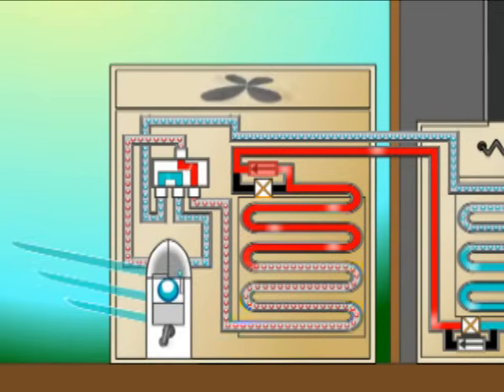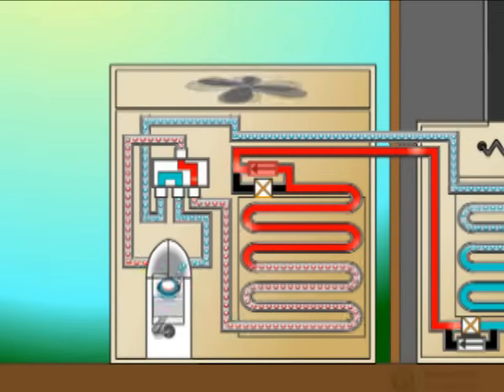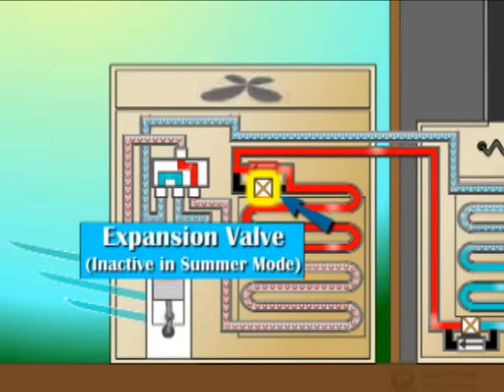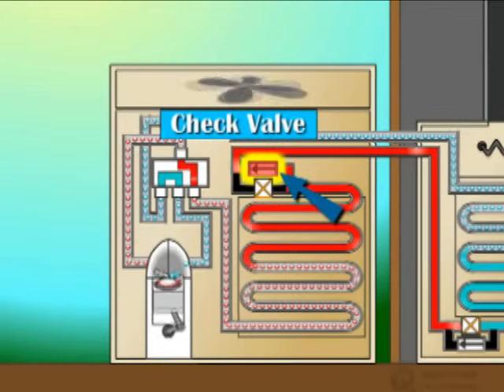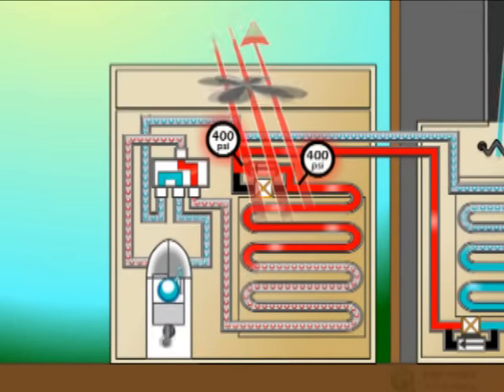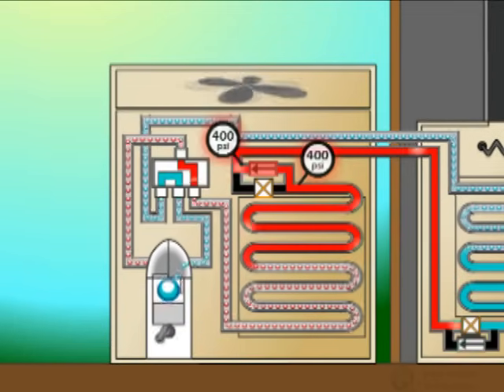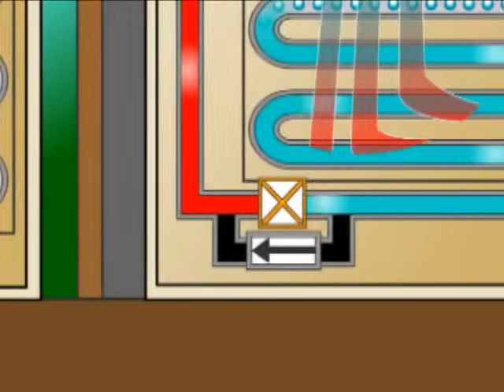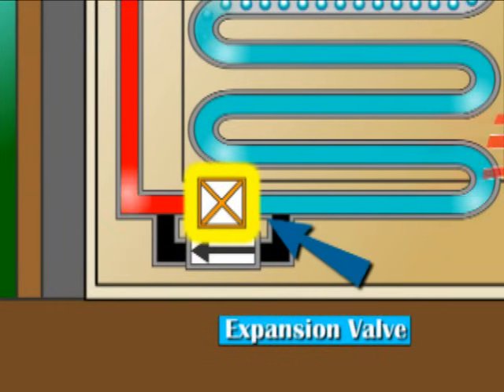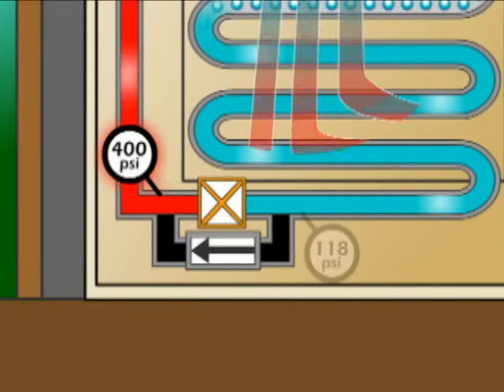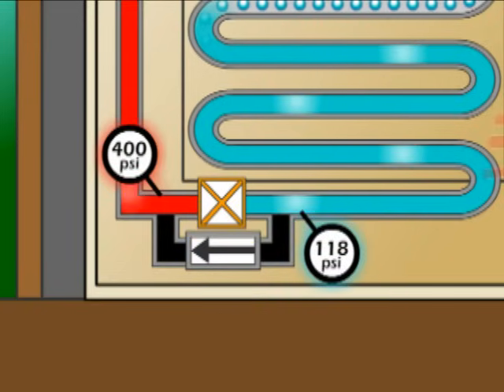The liquid refrigerant now bypasses the first expansion valve by means of a one-direction valve known as a check valve. The refrigerant, now cooler but still under high pressure, travels along the liquid line to the indoor unit where it is forced through the second expansion valve. This valve partially restricts the flow of refrigerant, creating the needed decrease in pressure, which allows the refrigerant to start evaporating.